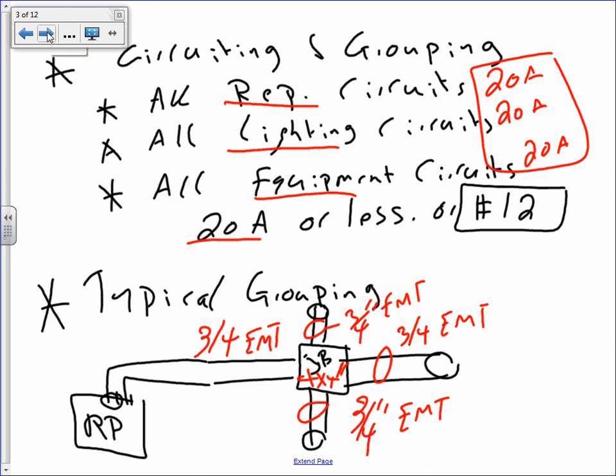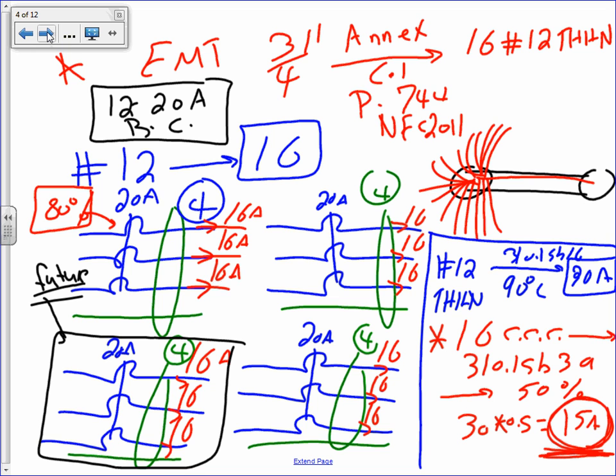Okay, now moving on. Let's go. Here's an example showing why I personally use 3/4 of an inch. Take this: I have an EMT conduit, 3/4 of an inch. How many conductors of number 12 THHN? From Annex C1, page 744, NEC 2011. If you go to 3/4 of an inch EMT, you're going to find that you can put 16 conductors in this conduit, maximum. Can I have thumbs up, chat? That's easy. From this Annex C1, 16 conductors. Why THHN? We're inside the building, right? We're doing branch circuits. Okay.